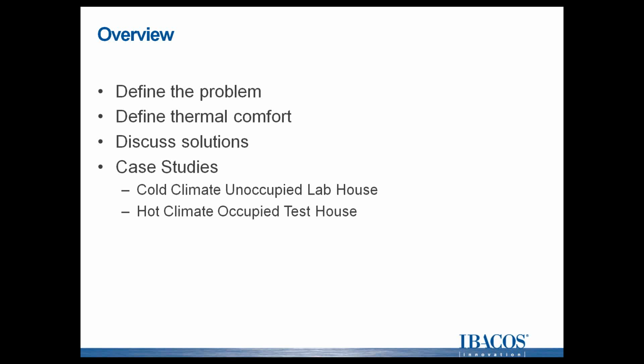Some of you may have seen this picture before. As we're moving loads lower and lower in production homes, the size of that load is reducing. But what isn't reducing is the overall square footage of these homes. So we see a house built to benchmark standards might have been a 7-ton cooling load, and the new house is now a 3-ton cooling load.